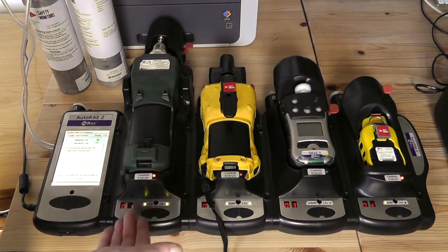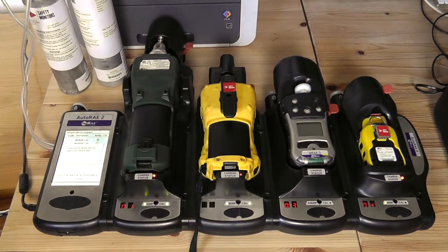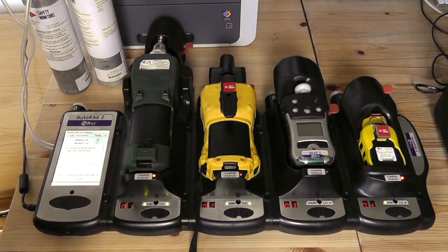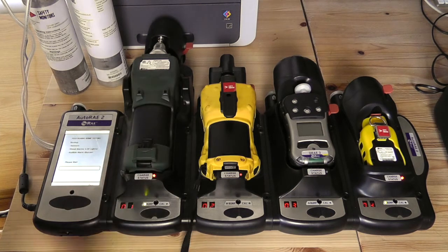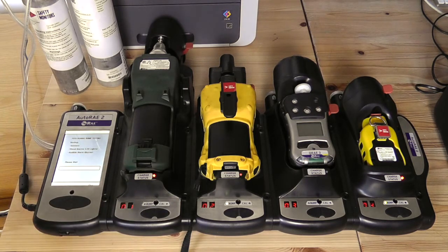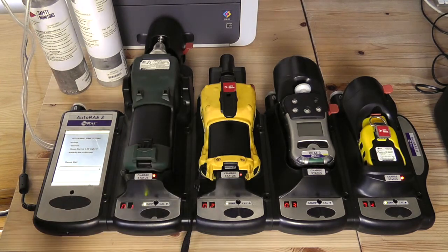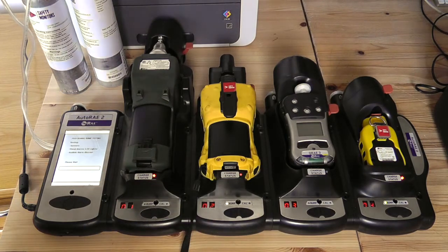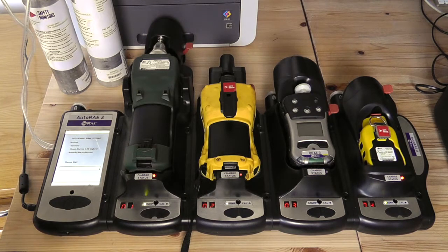It will sequentially calibrate the instruments in device order and let us know which instrument has been selected first. We'll now present and perform the bump test on the devices. At the end of this, we'll get a report to let us know whether it has passed or failed the bump test. We can automatically go into a calibration if it were to fail the bump test, or we can manually calibrate the device if it's over 180 days. The functionality is exactly the same on the QRAE 3 part of the dock.